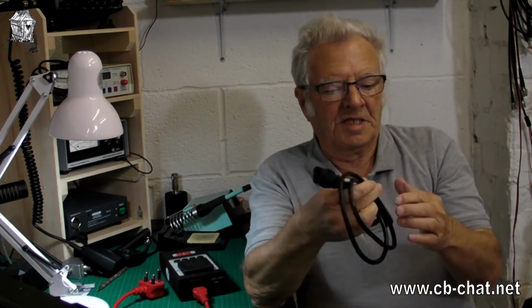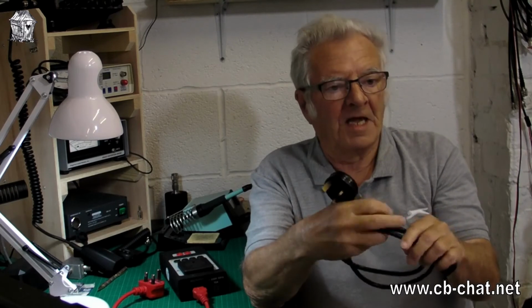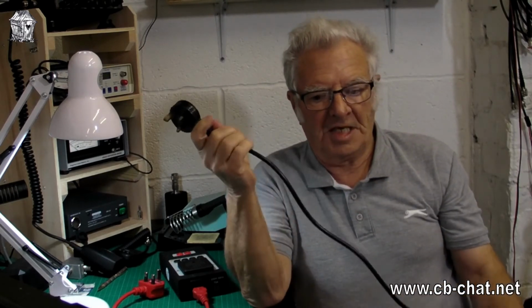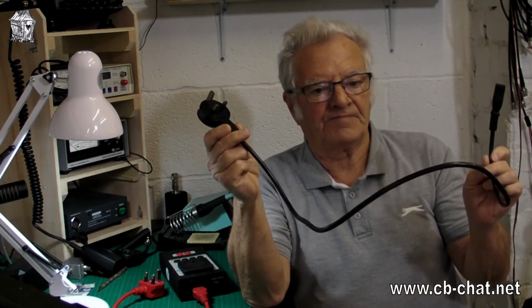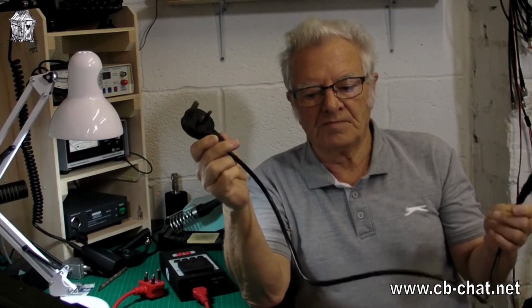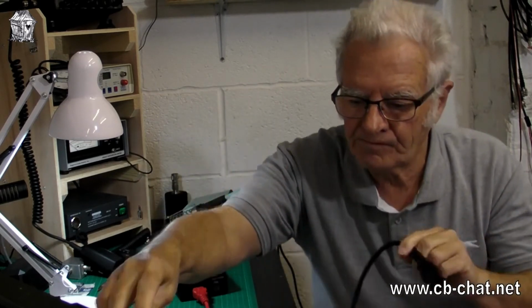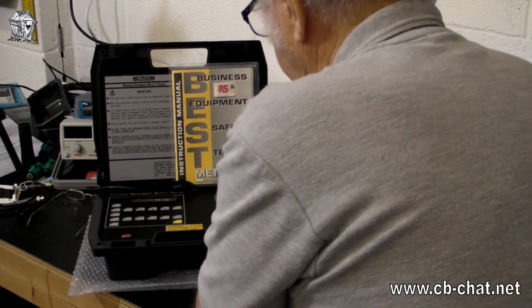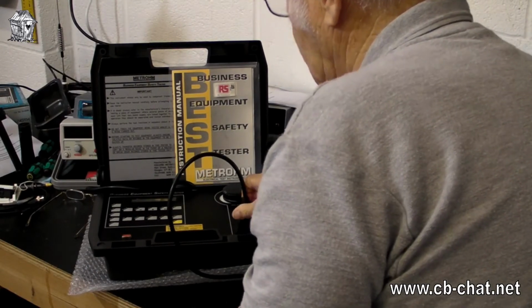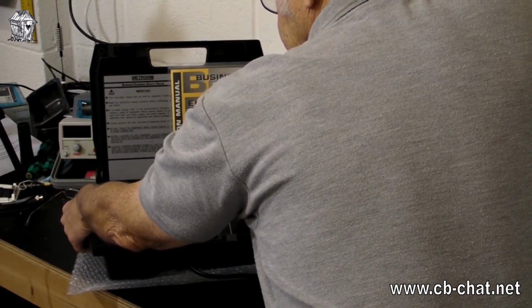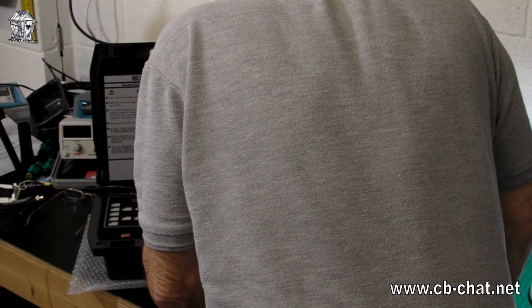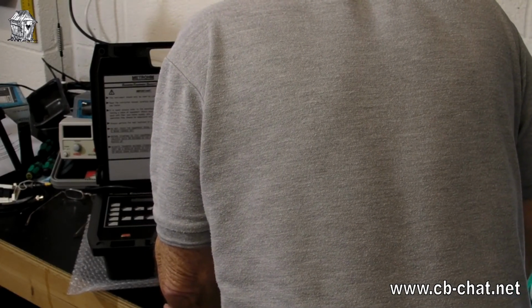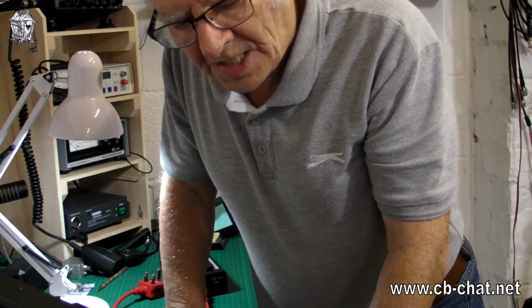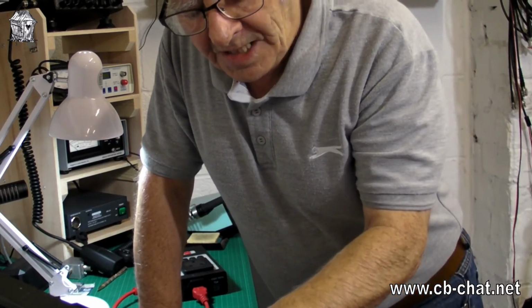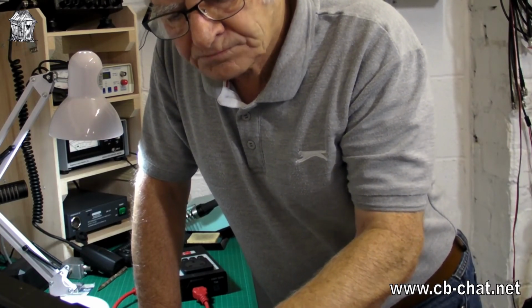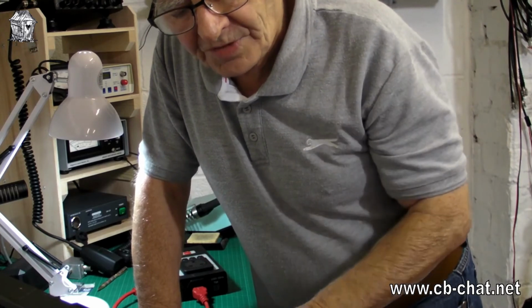Now this is scary. I bought something on eBay recently, an electric gadget, and it came with this lead. This is what was on it. So I'm now going to plug this lead in, and we're going to do a lead test, cord test. Press the button marked cord test. It says you can manually set it. It's set at a certain current and a certain value of ohms. So that's it, class 2. Press the execute button. Connect the cord, then press execute. Well, I've already connected it.